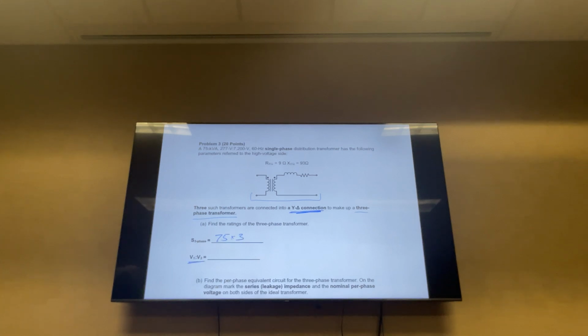And then on the voltage, we can draw it out, but we can also just talk through it and see what the voltage ratio here should be. So on the delta side, if I draw a delta, that means that this connection here will be connected here on the delta, line to line. So then whatever voltage is over here will be the line to line voltage. And we have that to be 7200 volts. And then on the primary we have a Y.